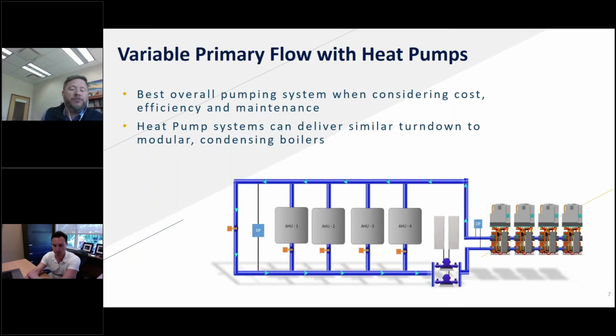And so when you compare those systems, at least from our perspective, and I know like-minded people can disagree on things, some buildings and some layouts really drive us maybe into a primary, secondary, or multiple tertiary loops from a pumping perspective. But if we look at the vast majority of installations or buildings, whether it's a boiler system, an air source heat pump system, or a chiller system, what we believe to be the most effective system is a variable primary system, because when you consider all factors, cost, efficiency, and maintenance, it delivers the best overall solution.